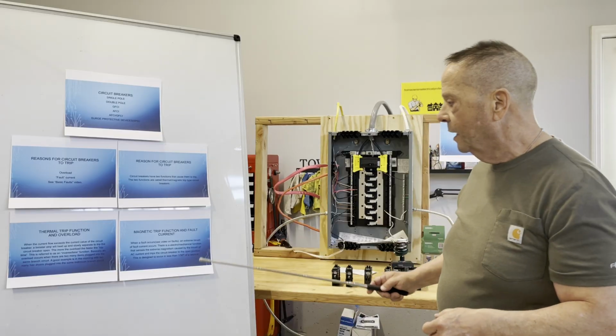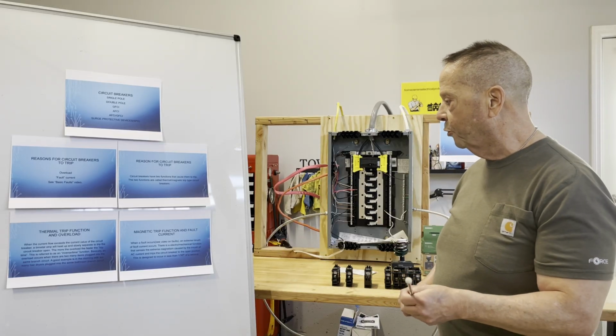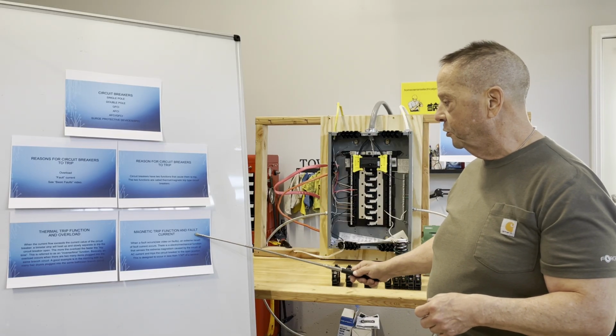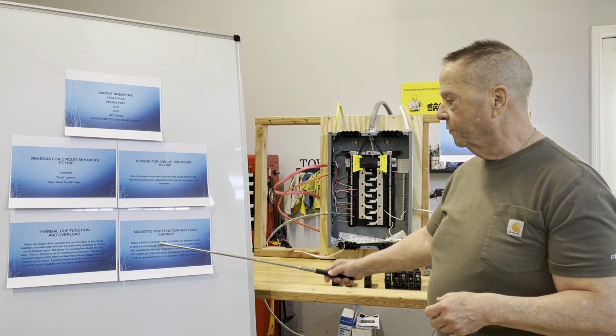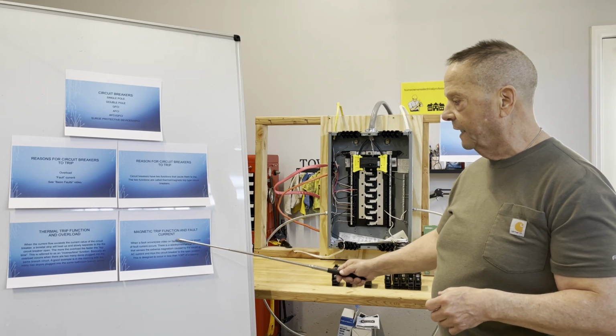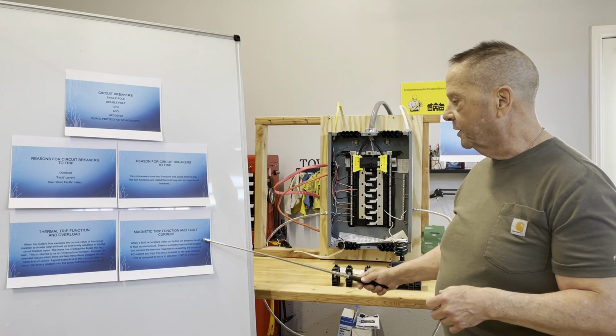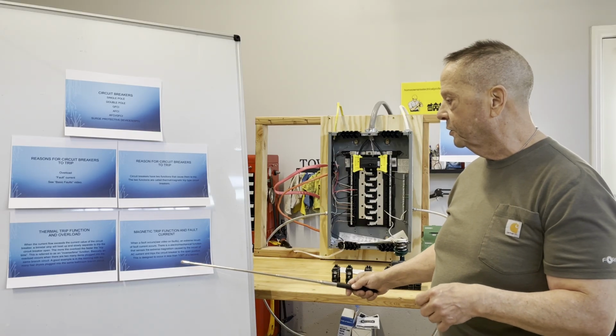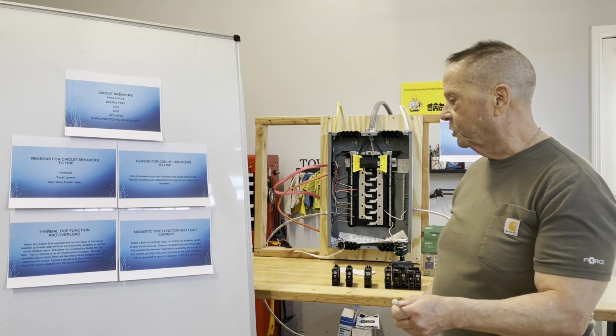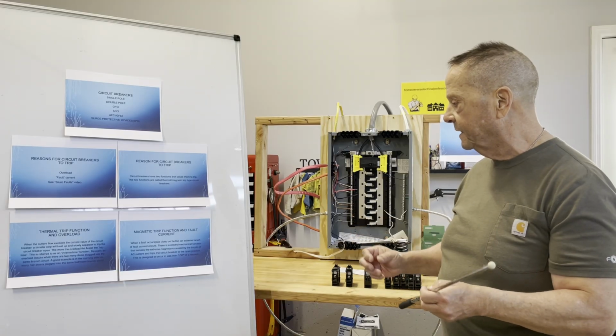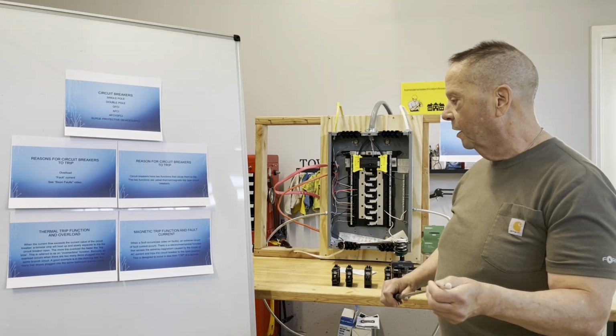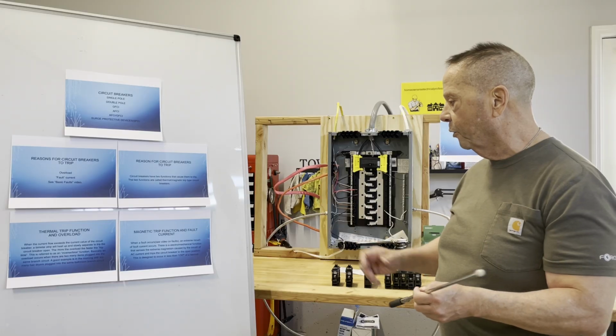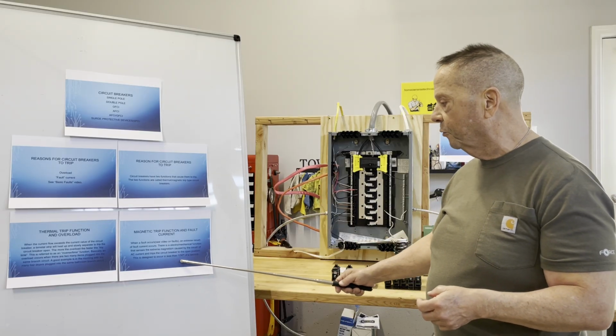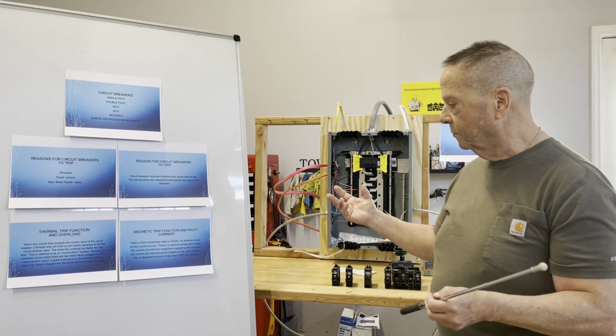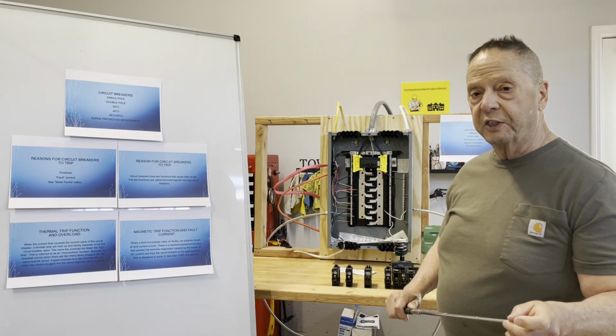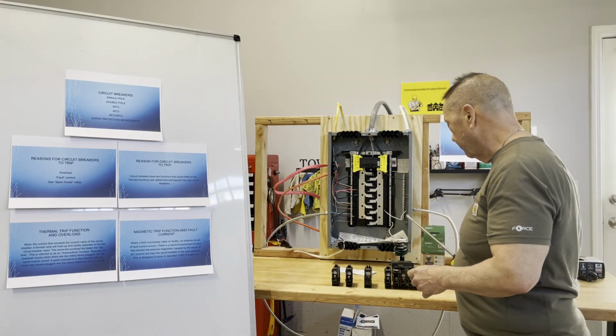same time. There's also what's known as the magnetic trip function, and that trip is used when there's a fault current. When fault current occurs, again, see those videos on faults, an extreme inrush of current occurs. There is an electromagnetic function that senses the extreme magnetism caused by that inrush of the AC current, trips the circuit breaker, and that is designed to occur in basically 1/30th of a second or less, okay? It's a very quick thing.